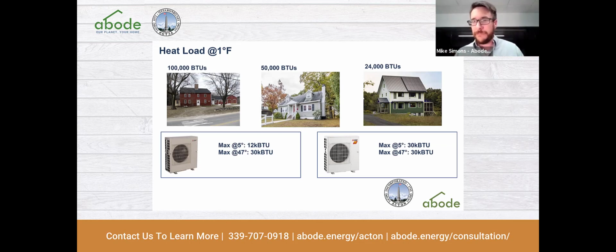There's going to be rooms with comfort, where one room is going to be more comfortable than another. So having possibly 2 outdoor units could also be really good, because it could give you a control strategy. In the summer, I'm just going to run the unit tied to my upstairs and cool that space. All that cool, dry air will drop down onto the 1st floor. In the wintertime, on the more mild days, I'm just going to run the one on the 1st floor and let all that warm, buoyant air rise up. When you actually do that, you end up running these systems in a very efficient way. So that's one way to go about doing it.